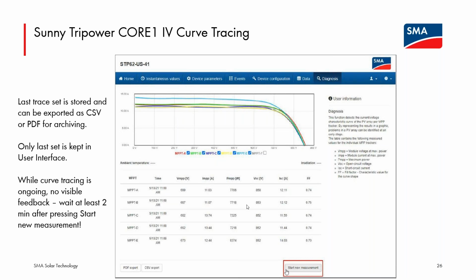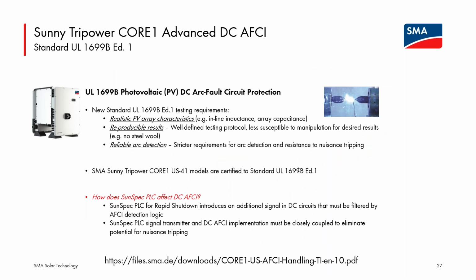Again, you have the inverter working when you click Start New Measurement. So don't turn anything off. The inverter should be in operation. AC and DC should be on. Go ahead and start new measurement. Again, it'll take each tracking channel offline while it performs the curve. So roughly 2 minutes, you will be taking off 1/6 of production and driving it to different spots. But you'll get this data without having to tear apart the array, which I think is very, very useful.